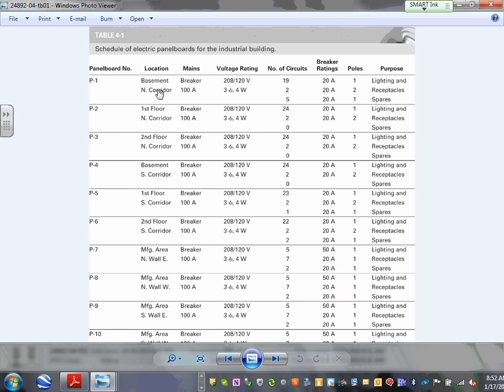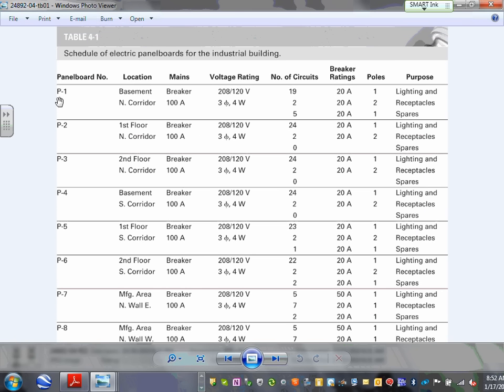And this is all basically the panel schedule that they have. Panel 1 located in the basement, north corridor. The main breaker for it is 100 amp. The voltage is 208/120, 3 phase, 4 wire. There are 19 circuit breakers, 20 amps each, single pole. 2 circuit breakers, 20 amps, 2 pole, and 5 circuit breakers, 20 amps, single pole, spare, and lighting and receptacles.